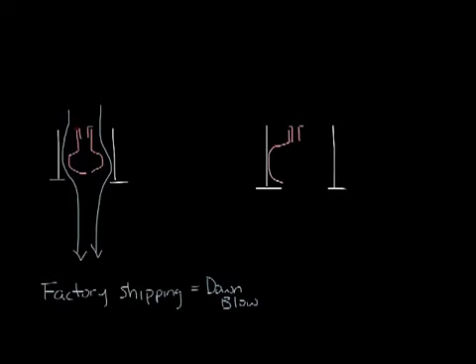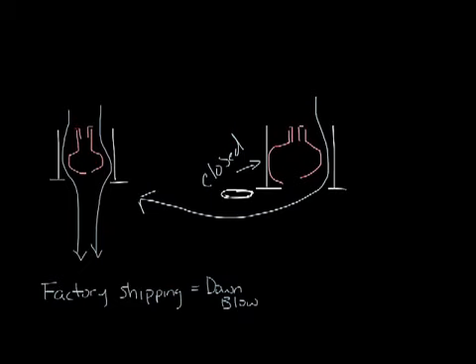So now if you look at the pattern controllers you kind of want something like this where one is all the way up against the side and the other one is pulled down to the center. What happens here is you're dampering one side. It's completely closed so the air can't get by. And as the air comes out you've got this low pressure zone right here next to the ceiling. And the air is going to come out and hold onto the ceiling and blow in this case to the left.